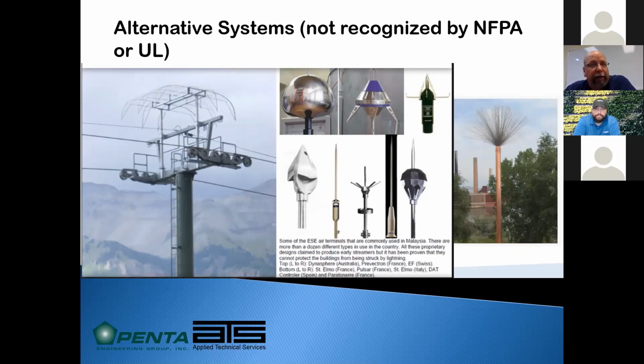We work with UL. We can have UL come out and inspect after us if we install the system, and then the annual inspections will ensure that it stays in accordance with that label, and then we'll have UL come back out at the 5-year mark and reissue the master label. Then we do issue reports. PENTA and ATS do the inspections. They issue the reports. We are a UL listed installer, so we can do all the repairs. We can also design and install new systems. We work with a manufacturer and we can get just about any component that's necessary to do any of this.